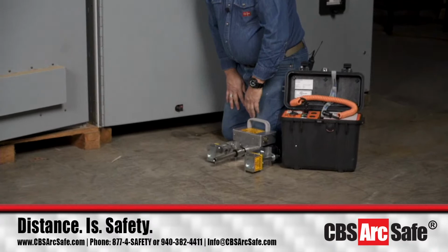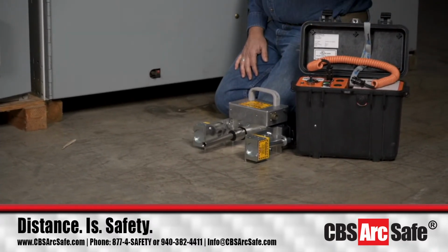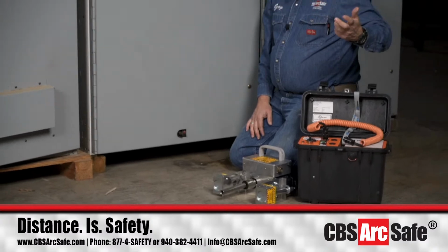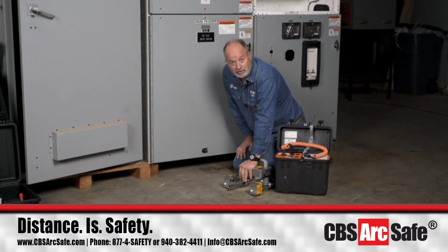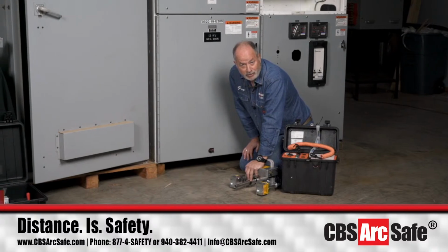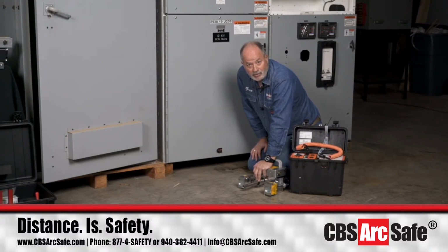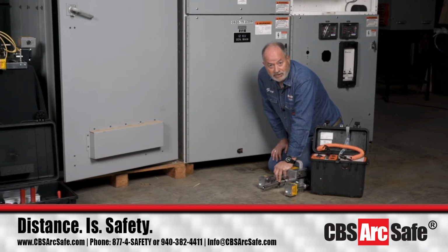This is a perfect torque clutch, and what we do is we work to rack a whole bunch of breakers, and then we take the values that we found for the maximum torque, and we add a couple of foot-pounds to that to set the clutch so we know that we're not going to hurt this stuff. So we'll normally set this clutch at about 3 to 5 foot-pounds above the highest force we've seen racking a breaker, so we're not going to let it put any more force into the racking mechanism than what we've seen in the warehouse.